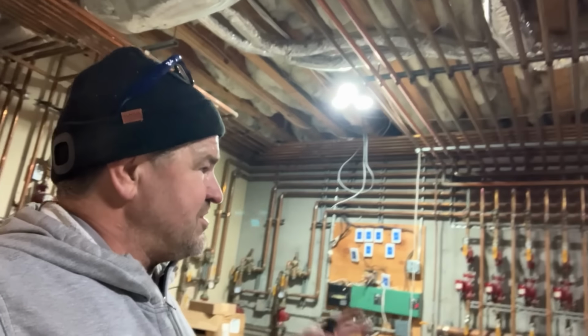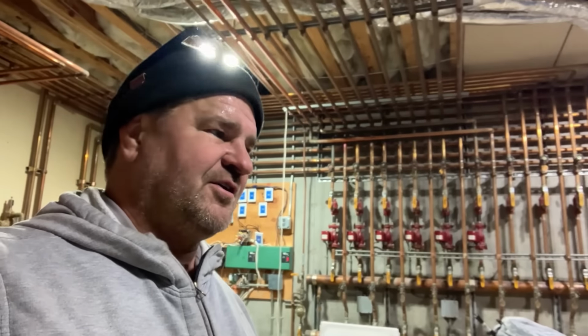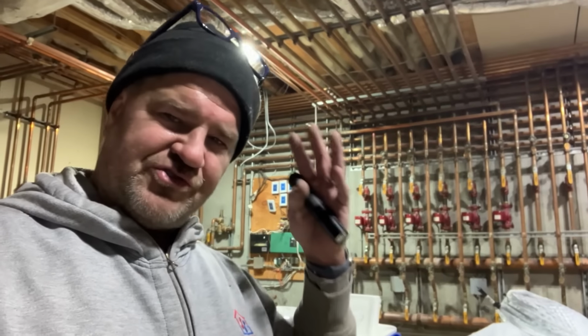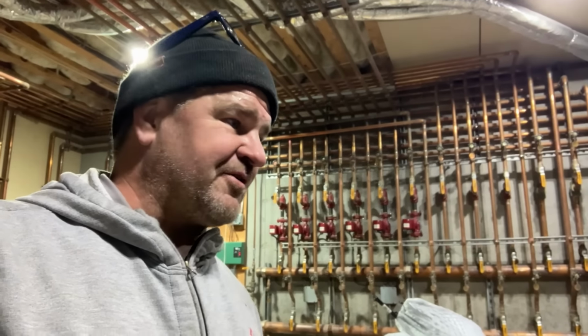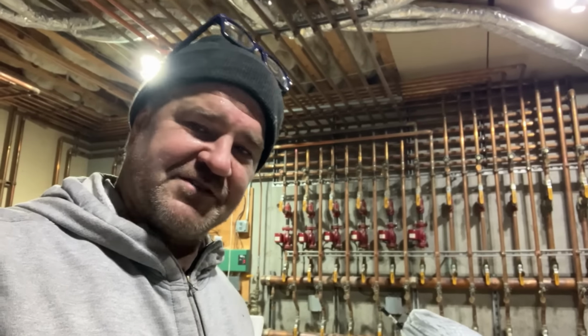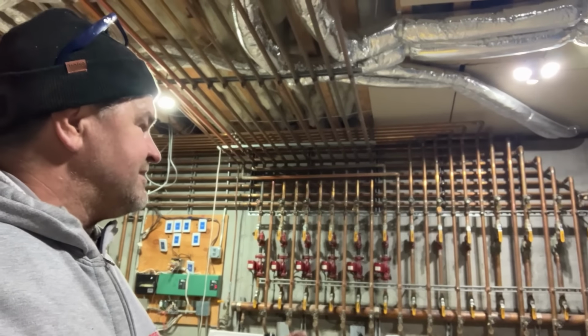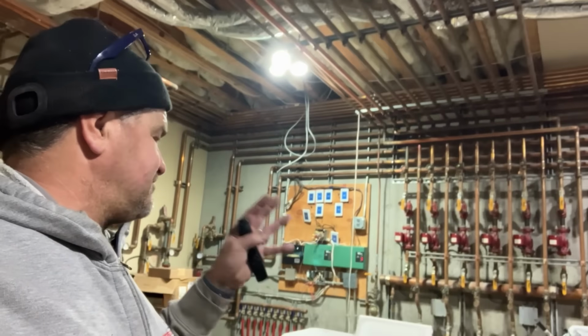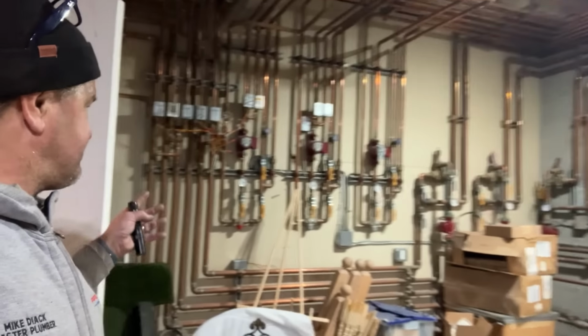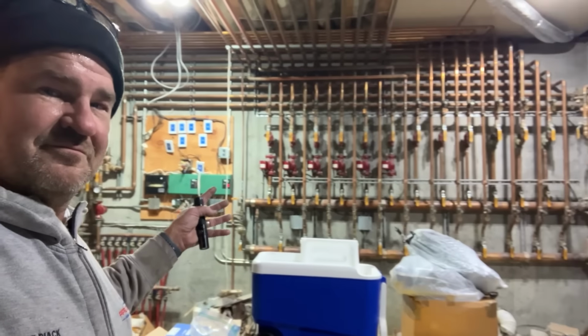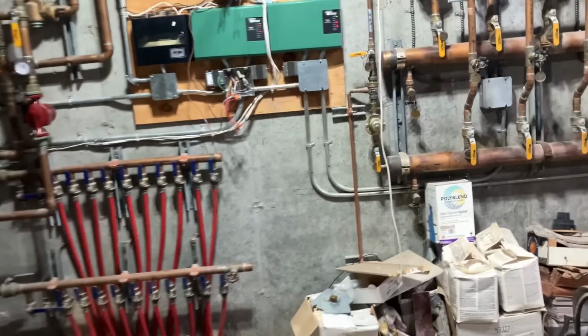It's 5:18. I'm in the boiler room, and Daniel asked me to add pressure to the system so we can purge out the air. Now, when you are lost, you utilize a map, your knowledge and your experience, and you look for the obvious. What we're looking for is a pressure reducing valve that's going to take domestic water and bring that into my hydronic side. And if you look everywhere here, did I pass it already? It's right there, folks, right here. And they're smart enough to put a valve.